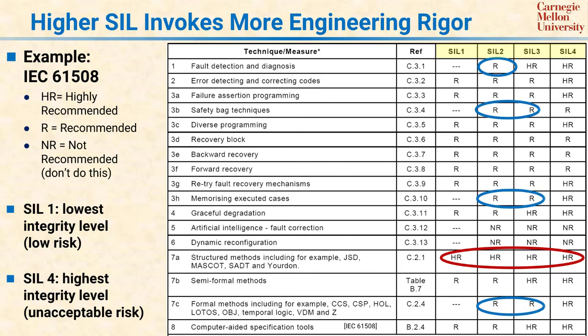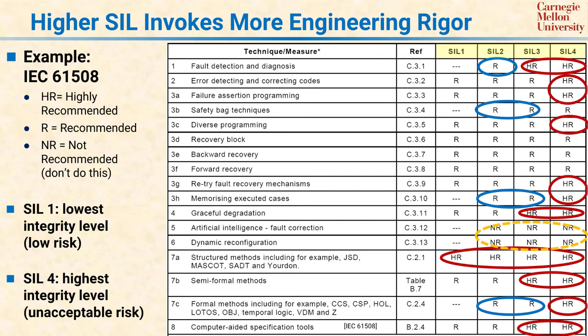At SIL 2, there may be significant injuries but no one is expected to die, so more techniques are recommended, but there are no additional highly recommended techniques. It is interesting that the use of artificial intelligence for fault correction and dynamic reconfiguration is forbidden starting at SIL 2, mostly because the system that is tested with these techniques is not going to match what the system in the field actually does due to reconfiguration. At SIL 3, people can die due to a system failure, and a significant number of additional techniques become highly recommended. At SIL 4, the consequences can be even worse, and many more techniques become highly recommended — which means you basically have to do them.